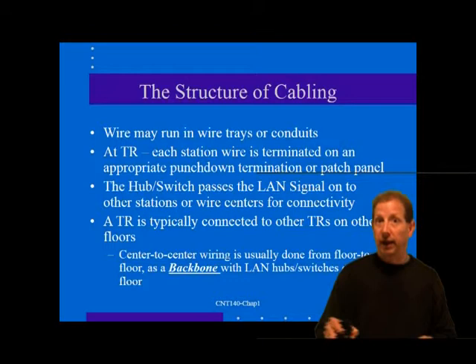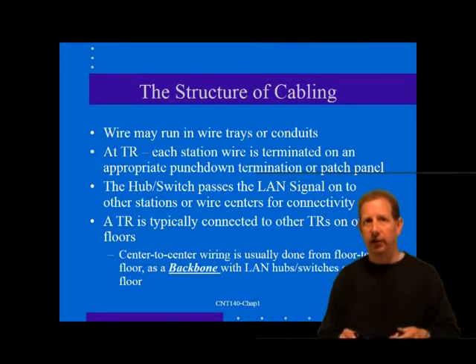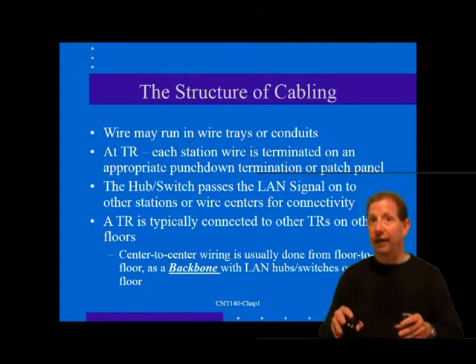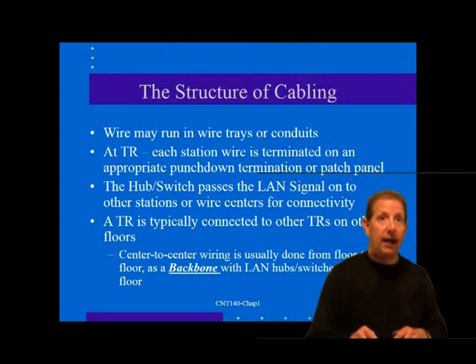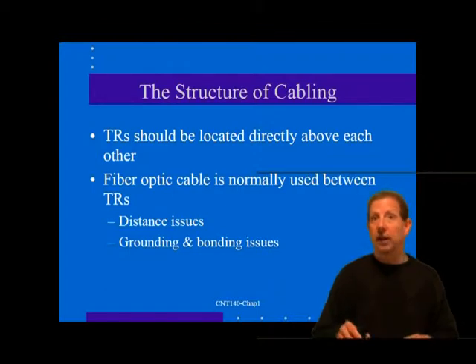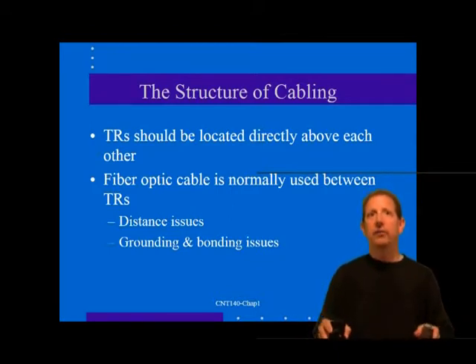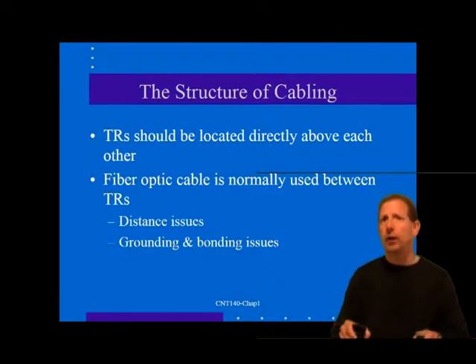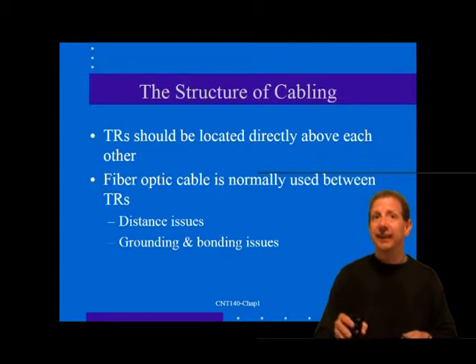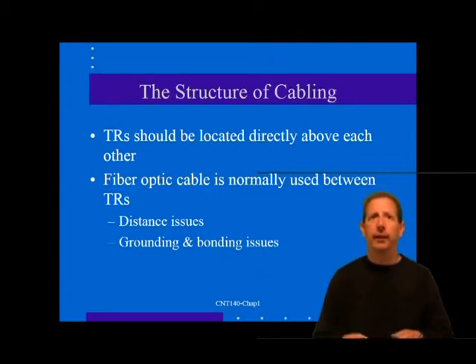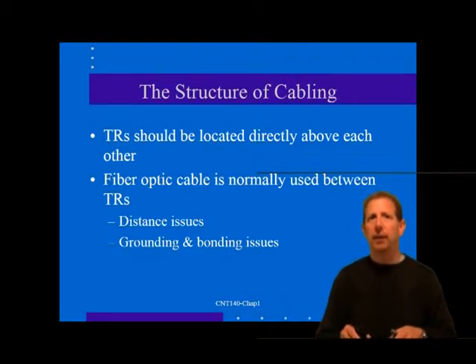In the telecommunications room, network devices such as a hub or concentrator are connected to each station cable. The hub passes LAN signals to other stations or wire centers for ultimate connectivity. A TR is typically connected to TRs on other floors via backbone wiring, floor to floor. In some cases it may be more effective to concentrate TRs on several floors into a single backbone concentrator. Fiber optic cable is sometimes a good choice for wiring between TRs, eliminating grounding and bonding concerns and allowing longer runs than copper.